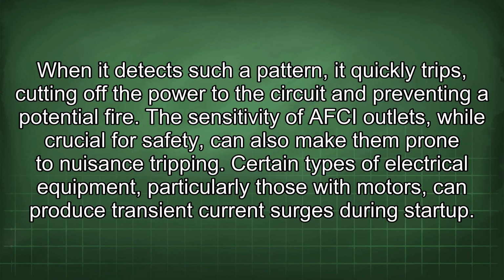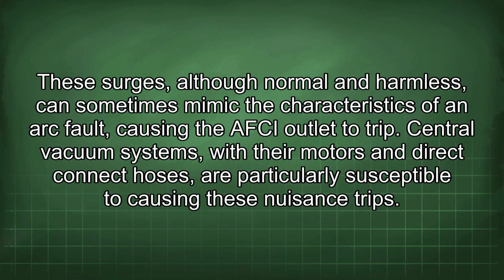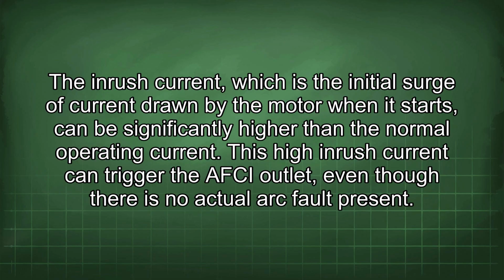potential fire. The sensitivity of AFCI outlets, while crucial for safety, can also make them prone to nuisance tripping. Certain types of electrical equipment, particularly those with motors, can produce transient current surges during startup. These surges, although normal and harmless, can sometimes mimic the characteristics of an arc fault, causing the AFCI outlet to trip. Central vacuum systems, with their motors and direct connect hoses, are particularly susceptible to causing these nuisance trips. The inrush current, which is the initial surge of current drawn by the motor when it starts, can be significantly higher than the normal operating current. This high inrush current can trigger the AFCI outlet, even though there is no actual arc fault present.